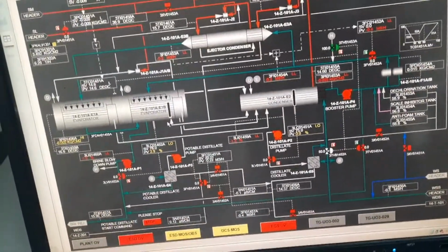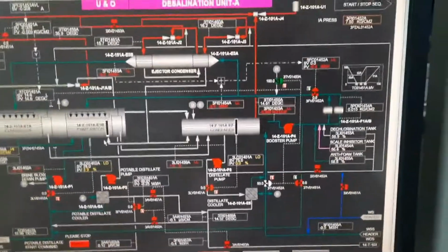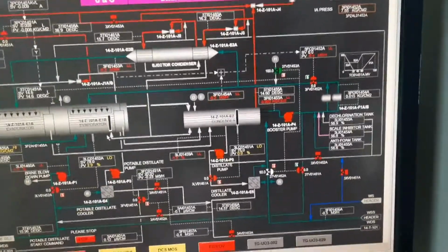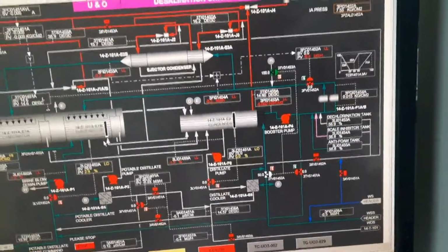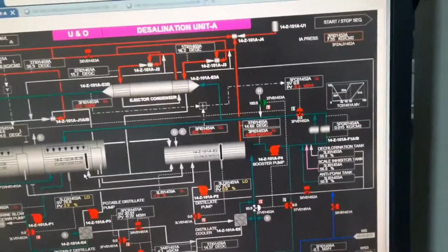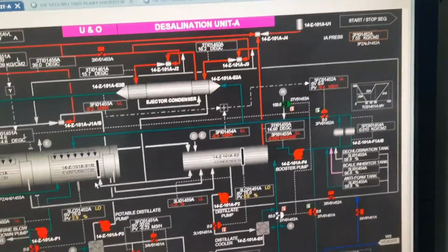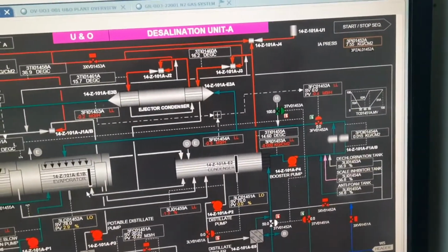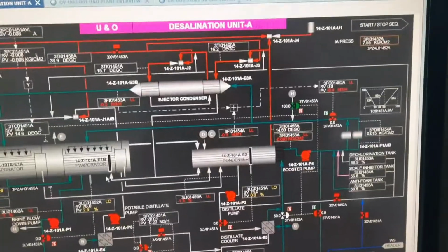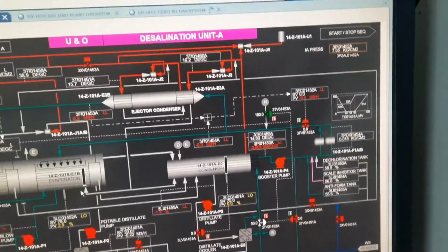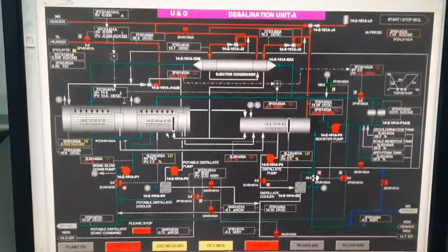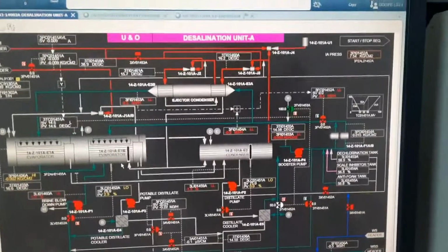We will enter the evaporator vessel. Anyone entering the evaporator vessel will check the tube bundle for any scaling or not. He will check and he will take photos. Okay, and if this evaporator is very dirty or has a lot of sand, then we need to wash it with a hose pipe. We need one connection from the service water area and then wash with this hose pipe to remove the dirt. Yes, for removing this dirt, first we need to wash with the hose pipe.